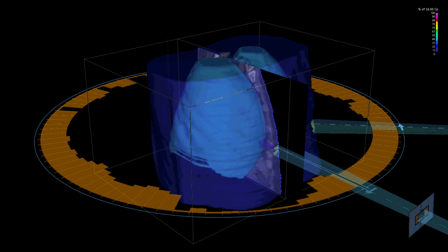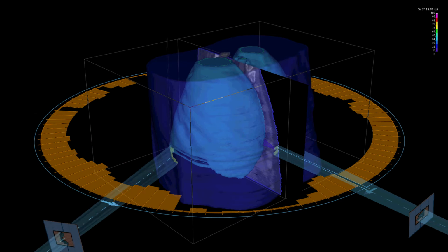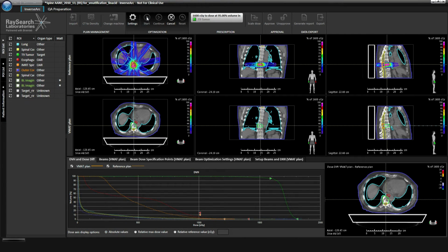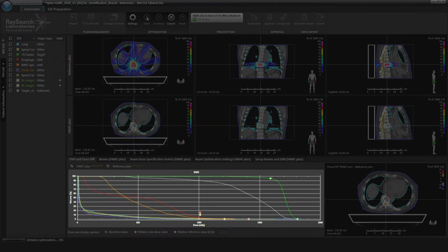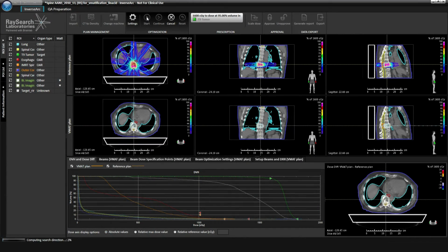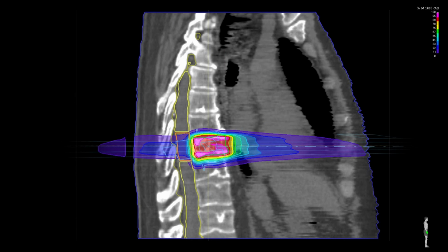The dose modulation option optimizes both the leaf position and the dose per segment, resulting in a treatment with simultaneous modulation of both the dose rate and the gantry speed. Inverse arc generates a plan that matches both the dose volume histogram and the dose distribution of the original reference plan. The dose is calculated with an advanced collapsed cone dose algorithm.